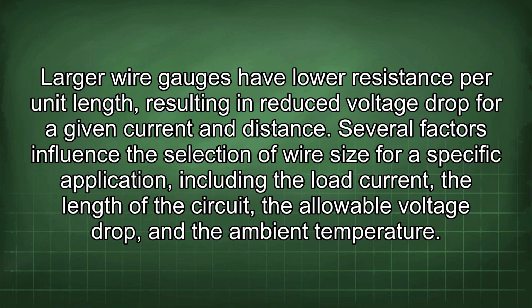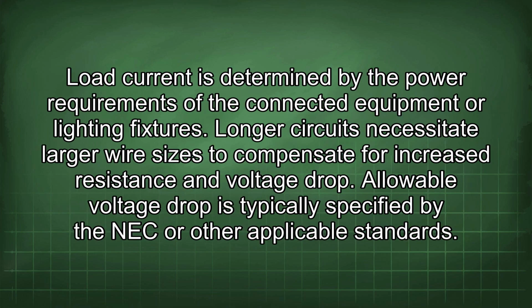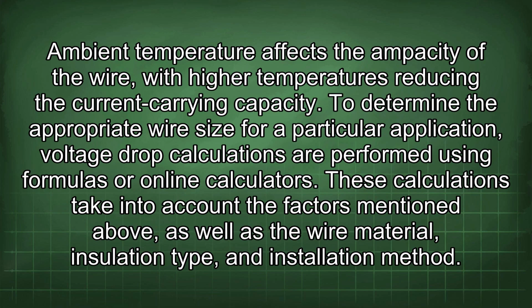Several factors influence the selection of wire size for a specific application, including the load current, the length of the circuit, the allowable voltage drop, and the ambient temperature. Load current is determined by the power requirements of the connected equipment or lighting fixtures. Longer circuits necessitate larger wire sizes to compensate for increased resistance and voltage drop. Allowable voltage drop is typically specified by the NEC or other applicable standards. Ambient temperature affects the ampacity of the wire, with higher temperatures reducing the current carrying capacity.